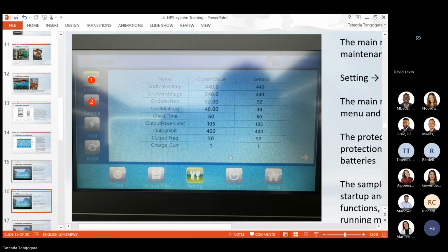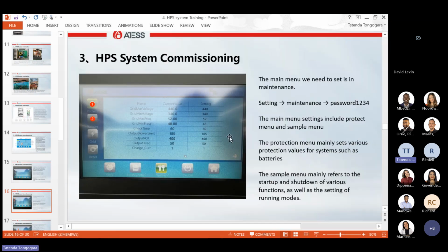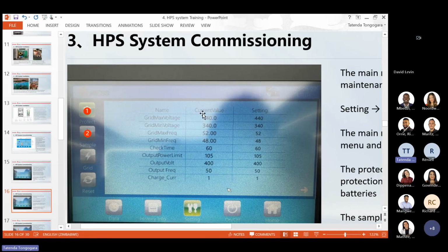Okay, so when you want to set up your system, click settings and then maintenance. The password is 1234. It's here in these notes. You can go through them when you're doing your installation. On the first page, those are our protect parameters. We have grid max voltage, grid minimum voltage, and our frequency. These are the max and minimum values. You cannot go above 440 and you cannot go below 340. You can set any values in between, but it's always best to leave these values like this, unless there are specific values that you want. You can set them how you want, but it should be within this range.